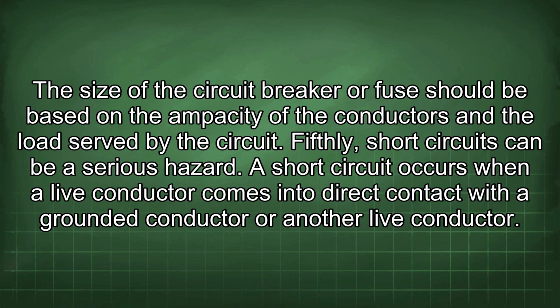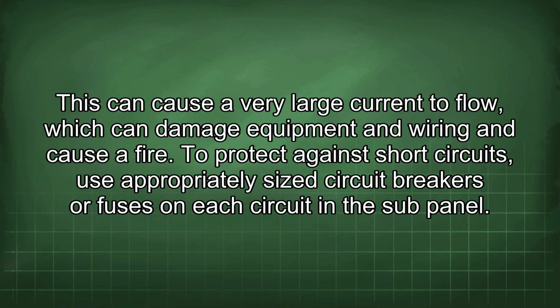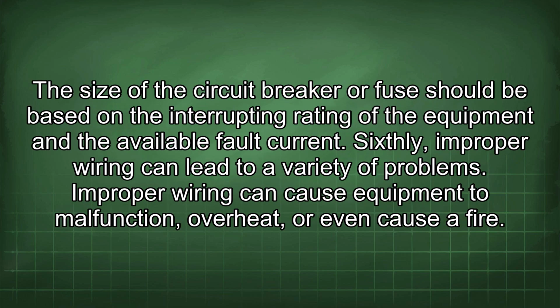A short circuit occurs when a live conductor comes into direct contact with a grounded conductor or another live conductor. This can cause a very large current to flow, which can damage equipment and wiring and cause a fire. To protect against short circuits, use appropriately sized circuit breakers or fuses on each circuit in the sub-panel. The size of the circuit breaker or fuse should be based on the interrupting rating of the equipment and the available fault current. Sixthly, improper wiring can lead to a variety of problems.